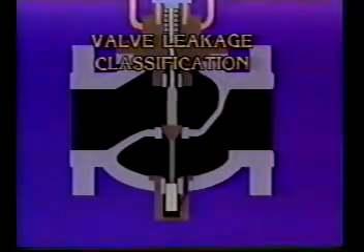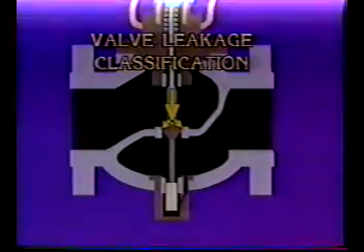The valve leakage classification also affects the amount of force the actuator must develop. A lower leakage tolerance may require a much greater actuator force. Rotary valves are also affected by static forces, but in a much different manner. In ball valves, such as this, as well as other symmetrical valves, there is no unbalanced static force that the actuator must overcome. However, the frictional force created between the seat and valve trim is extremely high. With a full ball valve, this friction exists throughout the valve travel and must be considered when sizing an actuator.